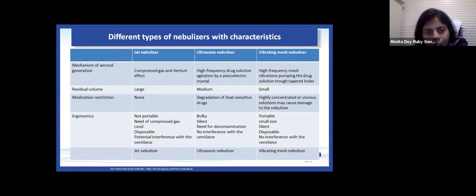And vibrating mesh nebulizer uses high frequency mesh vibrations, pumping the drug solution through tapered holes. Here the residual volume is very low, but highly concentrated or viscous solutions cannot be given by the nebulizer. So some drug delivery can be actually obstructed. But most of the bronchodilators that we give can actually be given by the vibrating mesh nebulizer. They are portable, small in size, silent and disposable, and there is no interference with the ventilator. So by and large, the ultrasonic and the vibrating mesh nebulizer are more ideal than the usual jet nebulizer that we are using.